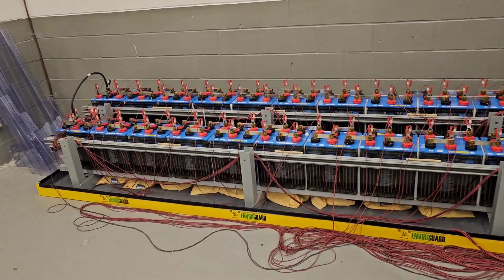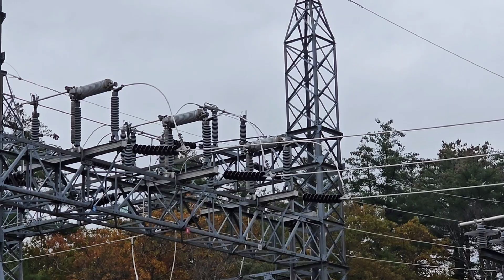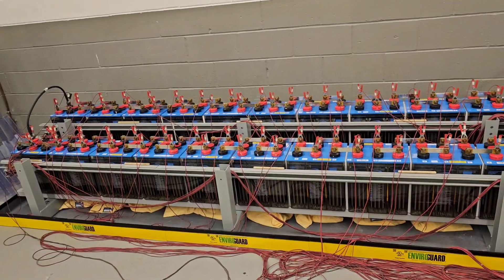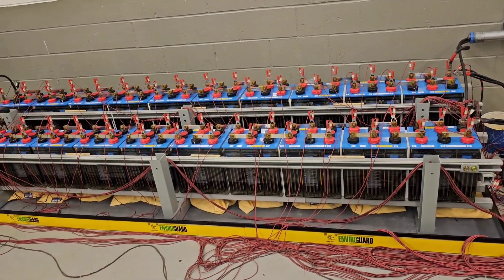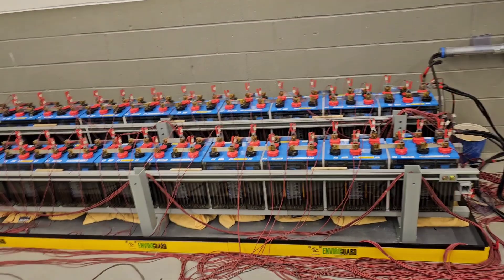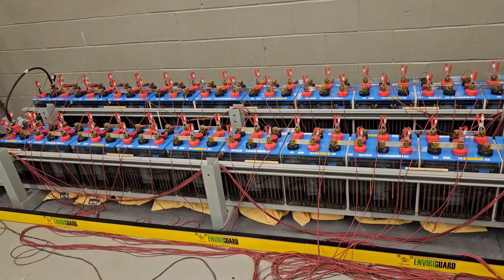Batteries are the heart of a substation — all critical systems run off battery power. Our particular systems have 60 cells, a little over two volts each, so you have a 125-volt bank for direct current that runs breaker power and control power.